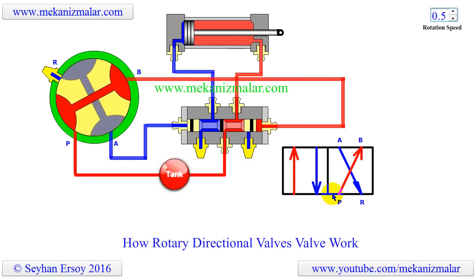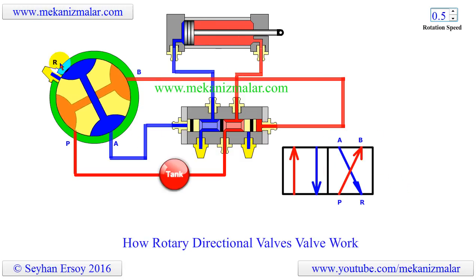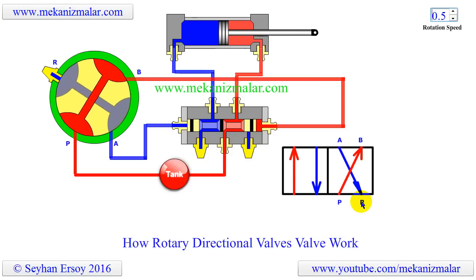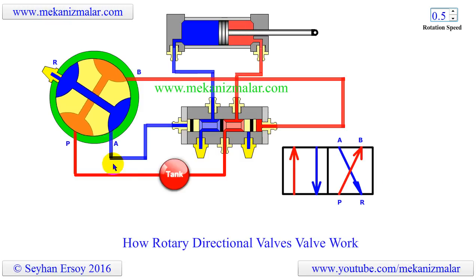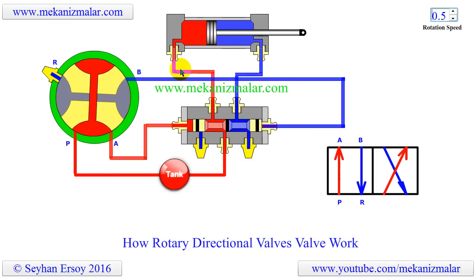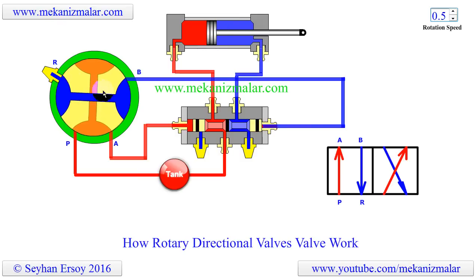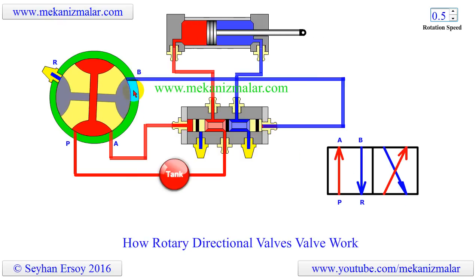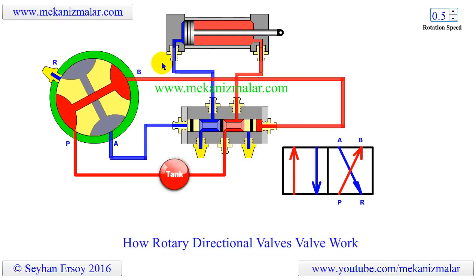Pressure port is labeled as P, while the exhaust port is labeled as R. A and B ports are connected to the pilot port of the 5-port 4-way air-piloted valve. By rotating the spool of the rotary valve, air can be sent to A and B ports of the rotary valve alternately to cause reciprocating motion.